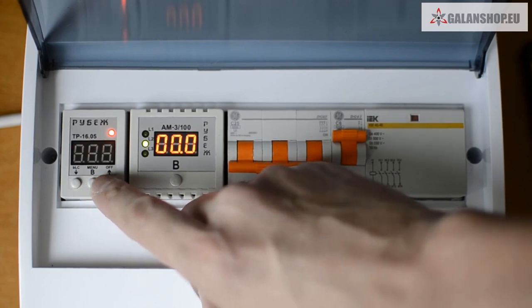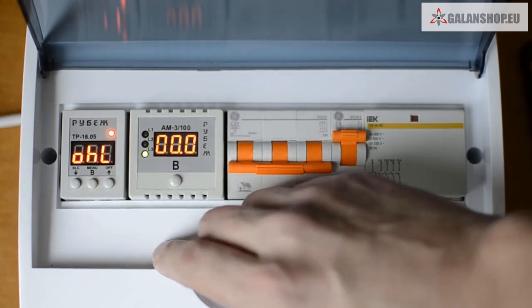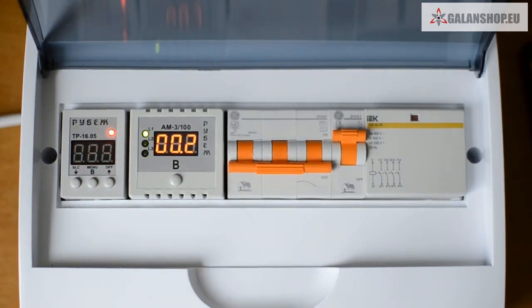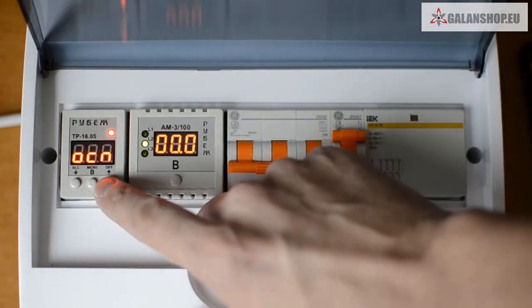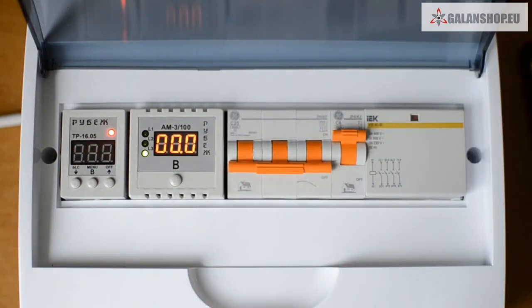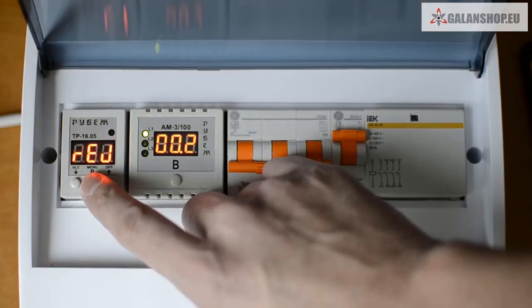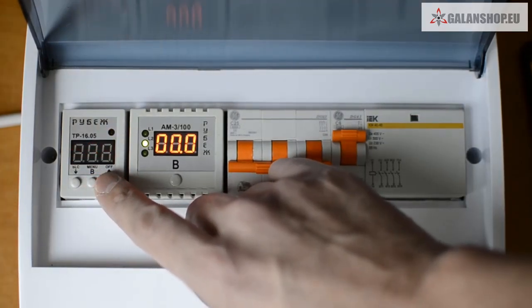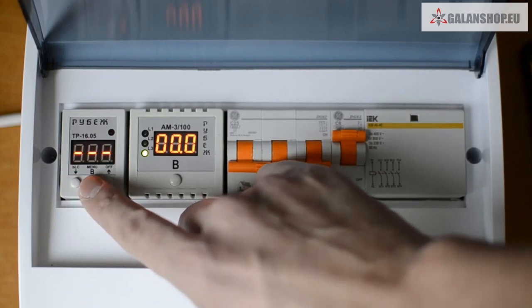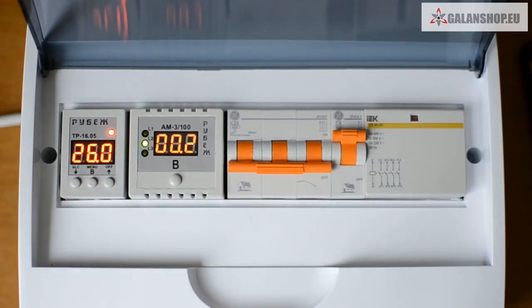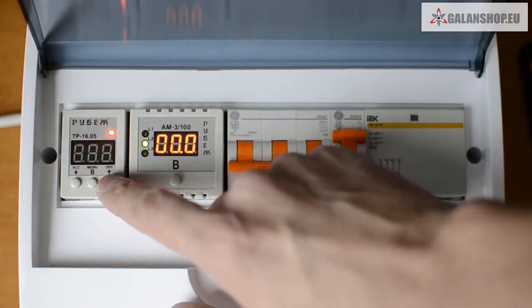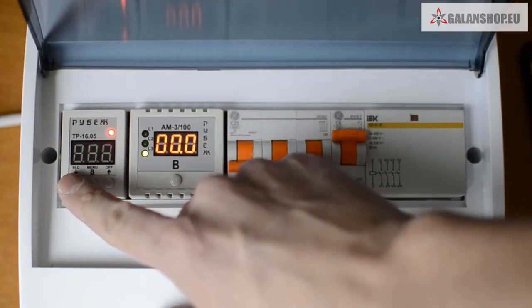How to set the requested mode. First, you need to open the controller's menu. In order to do it, press the B button and hold it for 2 seconds. Then press the same button shortly and choose the REJ menu. Then press this or this button and choose the regime. First of all, the heating mode, cooling mode, and interval mode. Accordingly, we are interested in the heating mode. The B button is used to fix it. As I already said, the controller has 3 modes: heating, cooling, and interval.